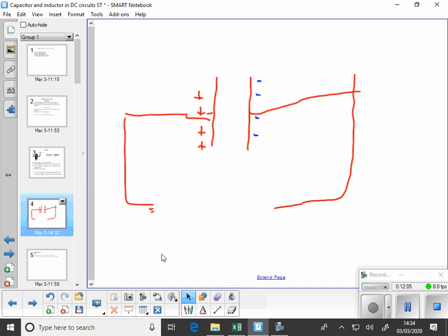They normally do try and make sure they discharge. On inverters, when the supply goes off, they automatically let a small relay drop out that connects in a discharge resistor. And usually on the front cover, the ones I've seen, it says, do not remove cover until this LED goes out, and you'll see that LED gradually fall away as the capacitor's discharged. Once that's gone out, it's safe to open the cover. You do need to be careful of them because they hold charge. Alright? All happy with that?